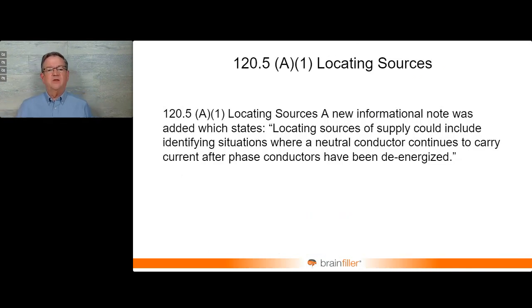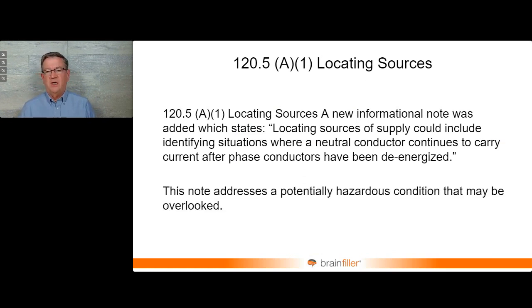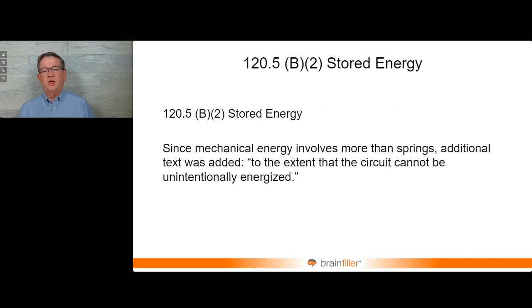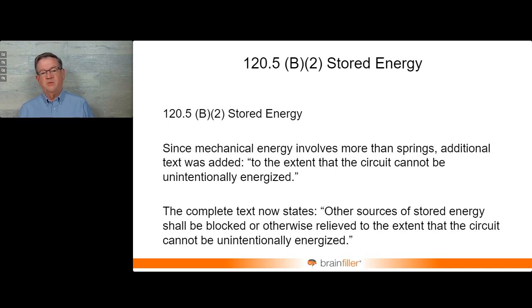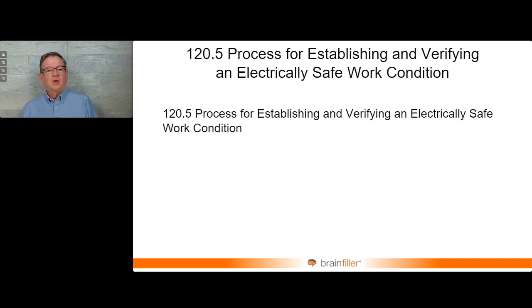And there was an addition about locating sources. If you have a circuit that could potentially have a neutral conductor still energized, depending on how the circuit is configured, you just have to be aware that the neutral could still be energized if you have multiple conductors in that circuit. Stored energy could be more than just springs, like a spring charge circuit breaker that could potentially reclose. And so there's a little bit of tightening up of the language here. Other sources of stored energy shall be blocked or otherwise relieved to the extent that the circuit cannot be unintentionally energized. And that's the goal. You don't want some other source of energy, pneumatic, spring, whatever it could be, that could cause a circuit to re-energize.